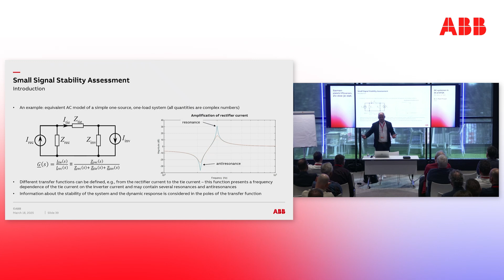And provide sufficient damping at these frequencies, because that's the solution. So here we enter the realm of small signal stability, where each of these resonances appears as a so-called pole in the complex plane. If the pole is on the right side, what's going to happen? It's going to explode. So it always needs to be on the left side, and ideally not too close to the right side. We say, as a rule of thumb, 12 degrees or 20% damping gives us a stable system. We see it drawn here. The orange line does not have enough damping.